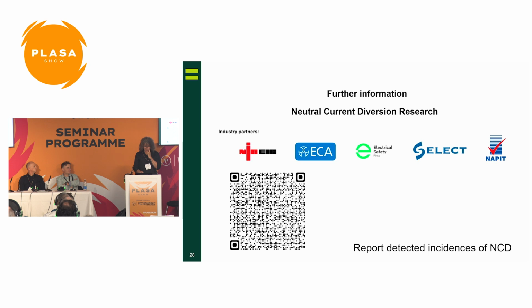And one other thing we're doing at the moment, the IET, we're doing research on neutral current diversion. And what happens here is where you've got a supply out from the street, and if the supply in the street has been damaged by corrosion, water's got into joints in the street, or it might be roadworks that have dug up part of the cable and severed that PEN conductor on the PME supply. So you've lost the connection to protective earth, you've lost the neutral.